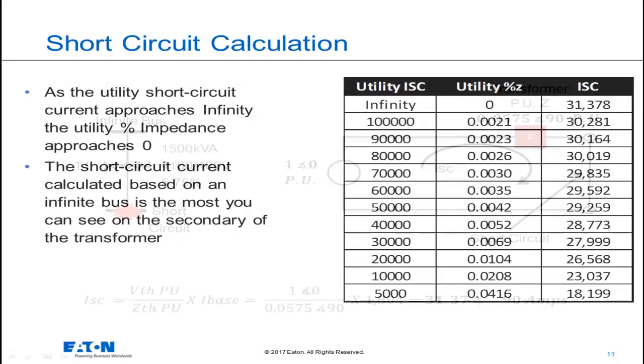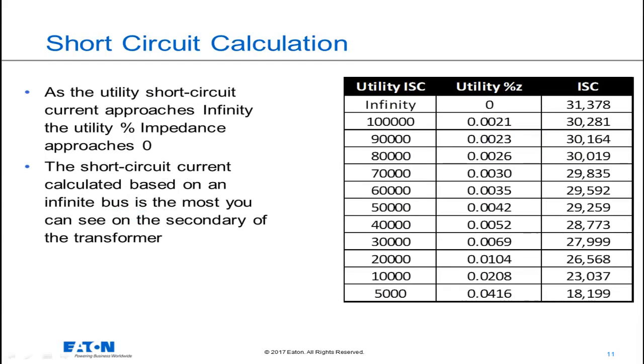The infinite bus short circuit current is calculated to be 31,370 amps. So this is a nice table as it gives us some more insight to short circuit current at the secondary of the transformer.